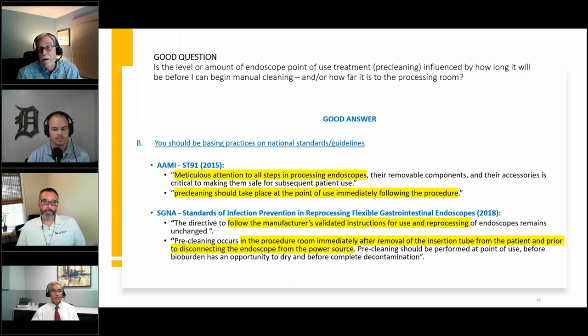The time and distance to further processing do need to be considered for what happens to the scope in the manual cleaning steps that follow. Processing staff need to follow manufacturer prescribed steps for delayed processing in those circumstances where the manufacturer's recommended time between the point of use treatment and manual cleaning is exceeded.